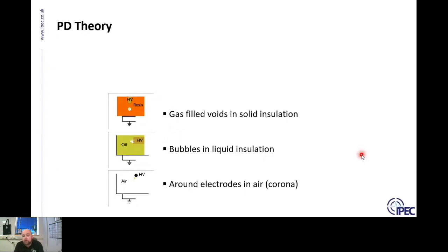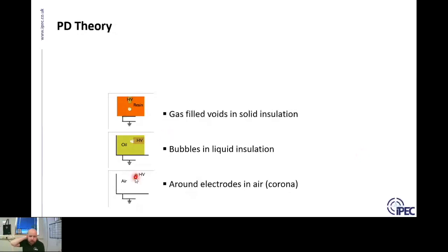It could also occur in oil or compound insulation where bubbles form, or around an electrode in air — such as at a cable termination. It is not surface tracking, and on a bushing or outside connection it can also be known as corona, which is less concerning.